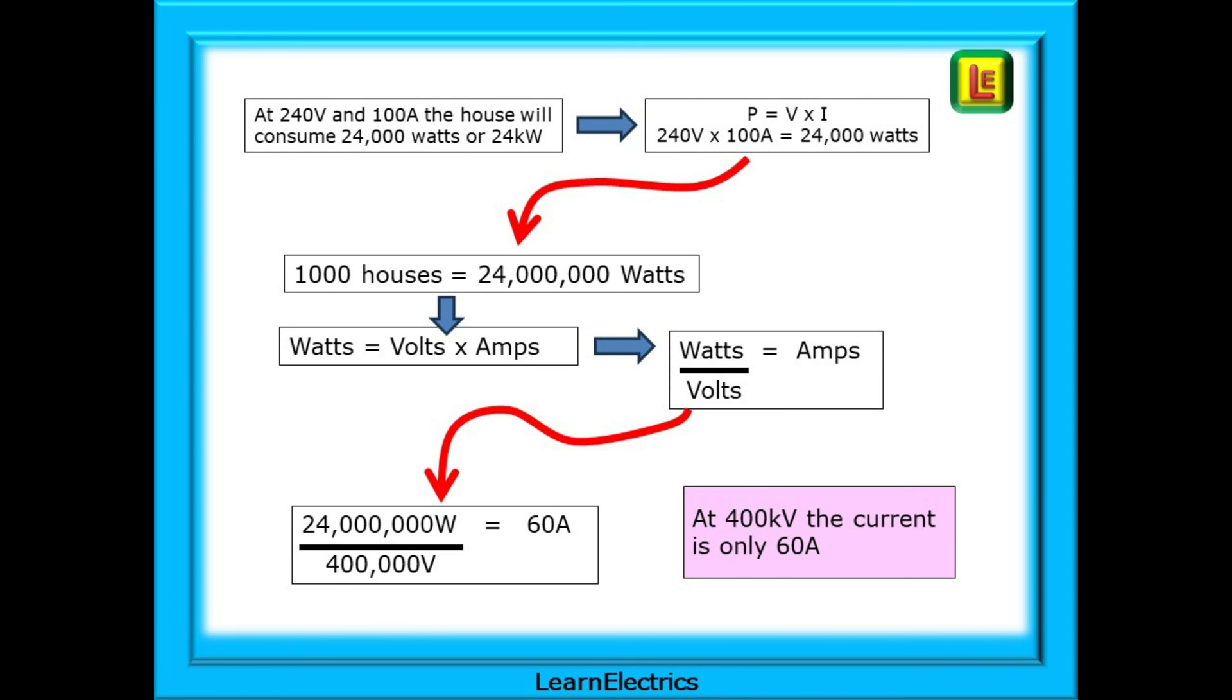So this is what we do. Some very easy calculations. At 240 volts and 100 amps, the house will consume 24,000 watts or 24 kilowatts. We know this from the power formula P equals V times I. So 240 volts multiplied by 100 amps is 24,000 watts. A thousand homes is 1,000 times bigger, so 24 million watts. We also know, ignoring transformer losses, that the wattage across a transformer stays the same. So 24 million watts on the primary or input side will be 24 million watts on the output side, the secondary. We can rearrange watts equals volts times amps to get watts divided by volts equals amps.